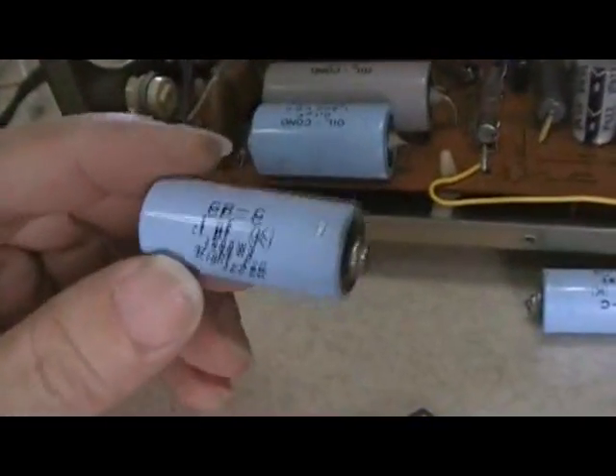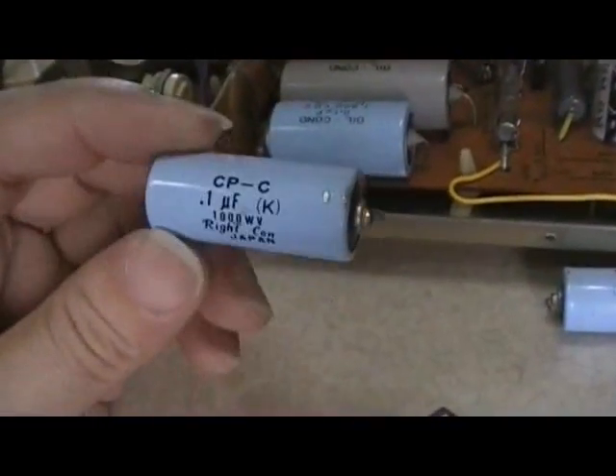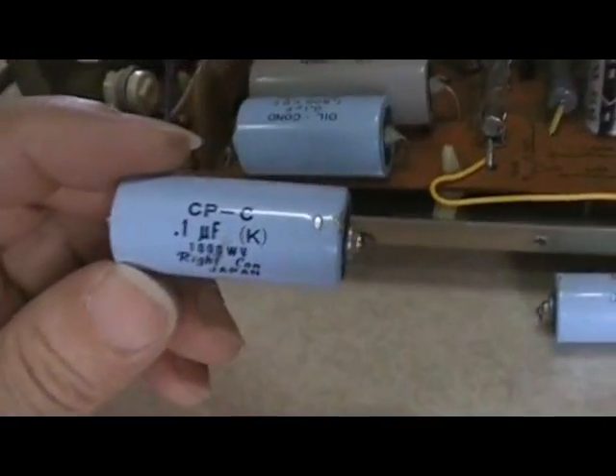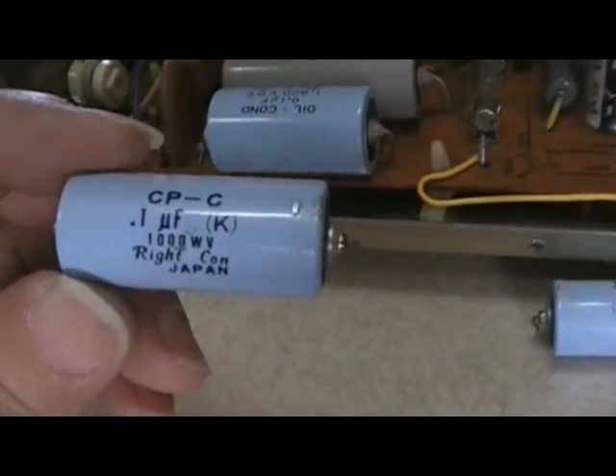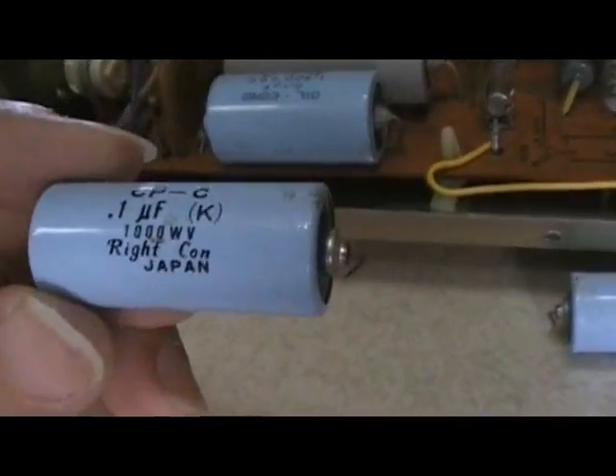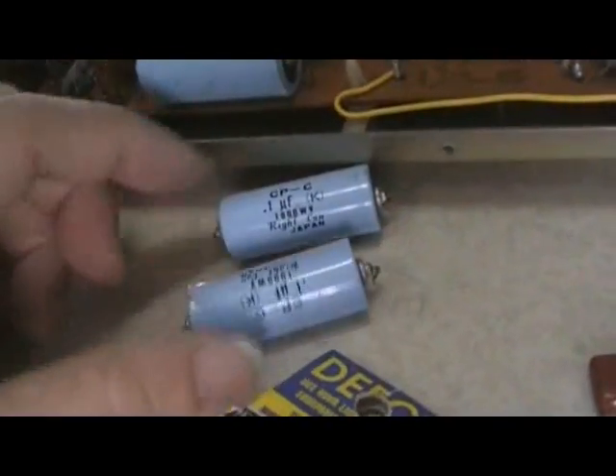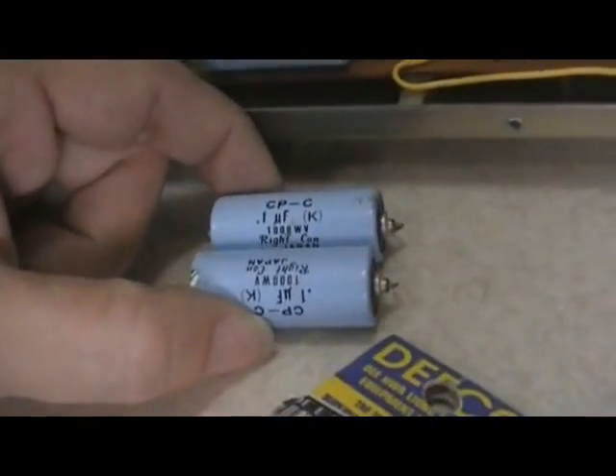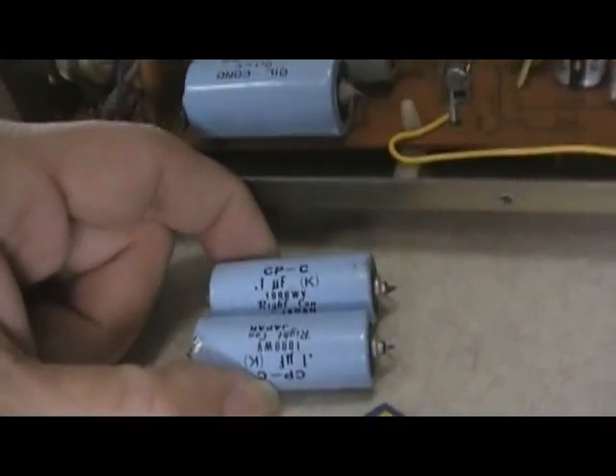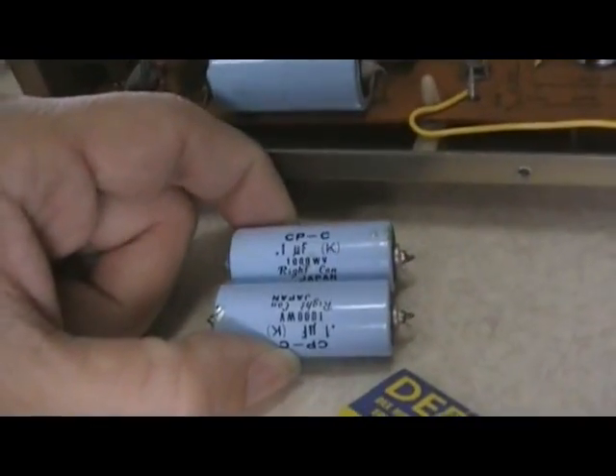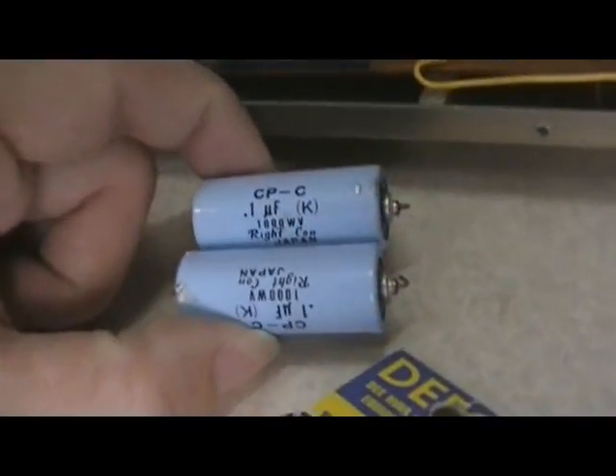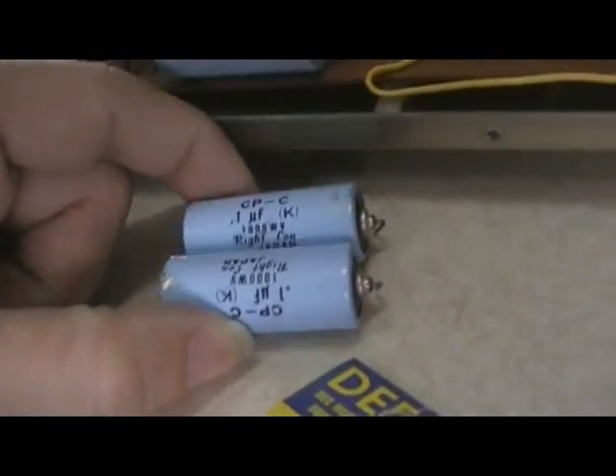This is the defective capacitor. This is a voltage doubler capacitor - it's 0.1 microfarad, 1000 volts. The two capacitors have open circuit, that's why I can't produce a very high voltage. Now it's very difficult to get this kind of capacitor.